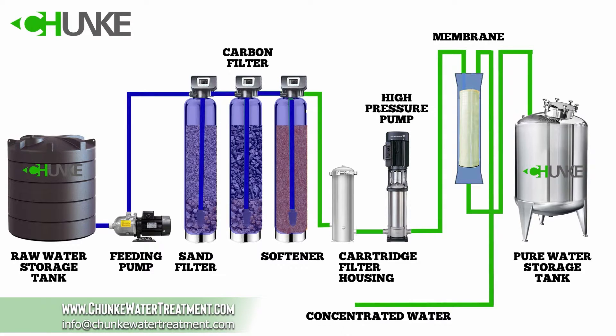After pre-treatment, our water is ready to go to the reverse osmosis membrane. Before the RO membrane, to ensure there are no particles in the water, it passes through a cartridge filter housing. We generally use a two or five micron PP cartridge filter.